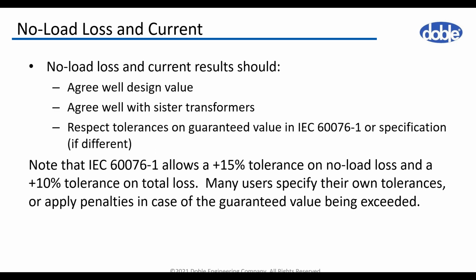Similarly to the load loss, we would normally expect no load loss to agree with design values and results from sister units. The no load loss and current should respect the specification and the guaranteed values. Also, IEC 76 part 1 allows a tolerance of 15% of no load loss and 10% of the total loss. But again, most of the clients specify their own limits, and if they are not met, then penalties apply.